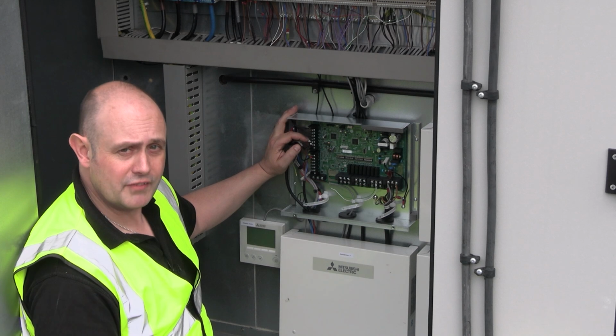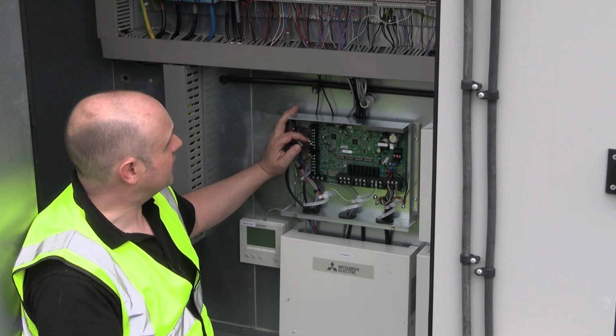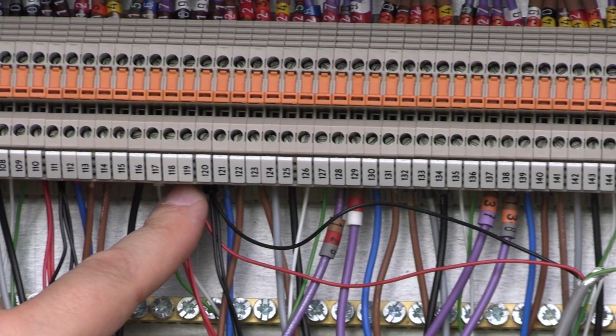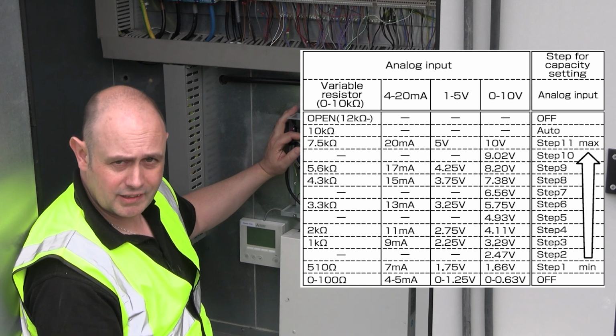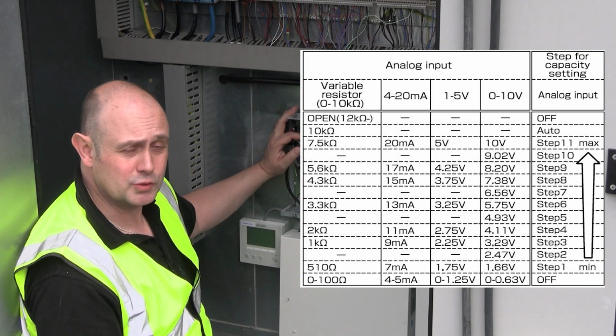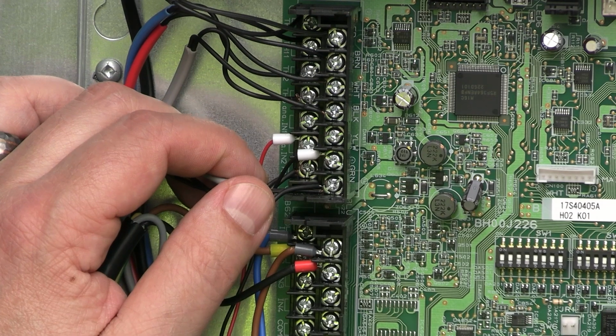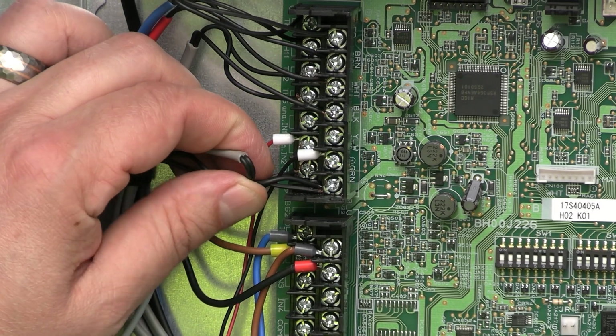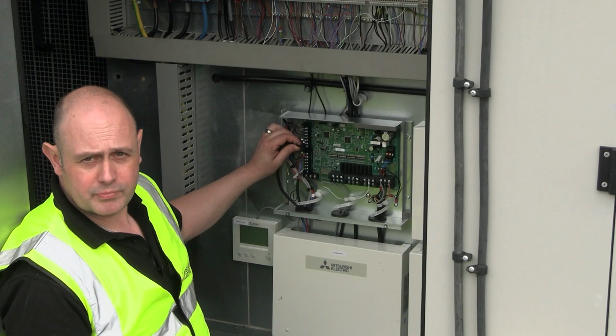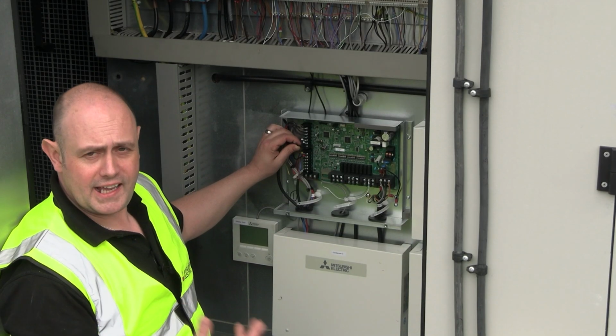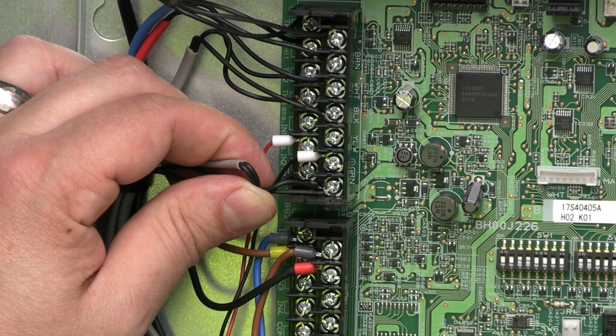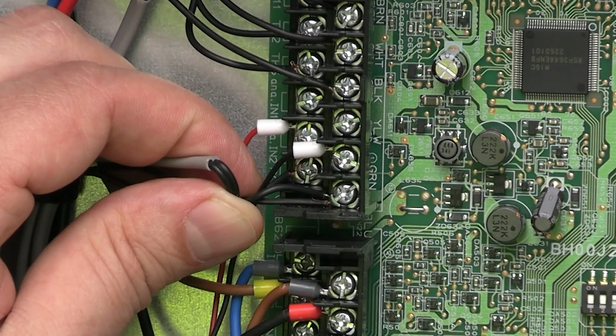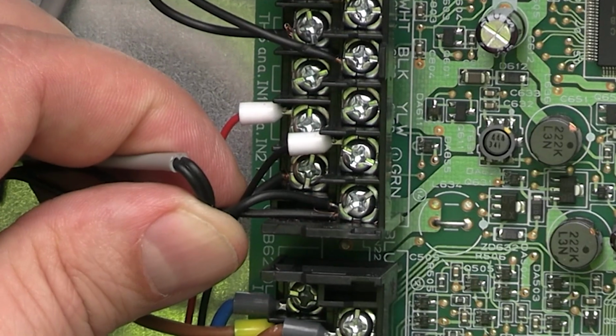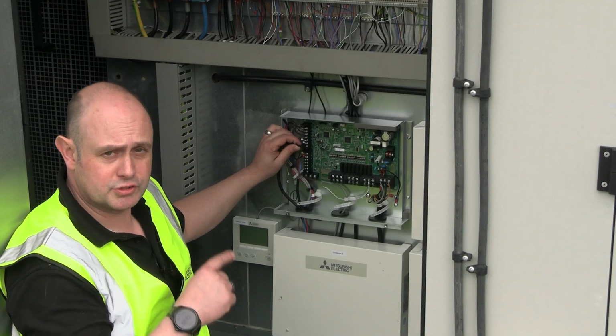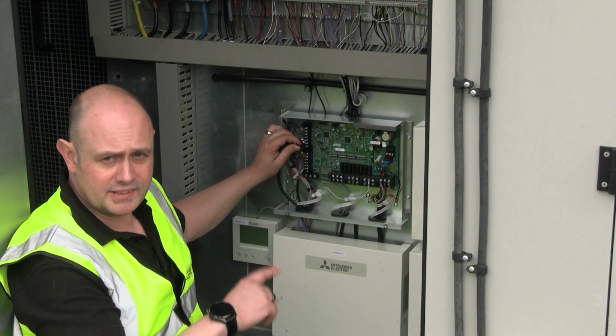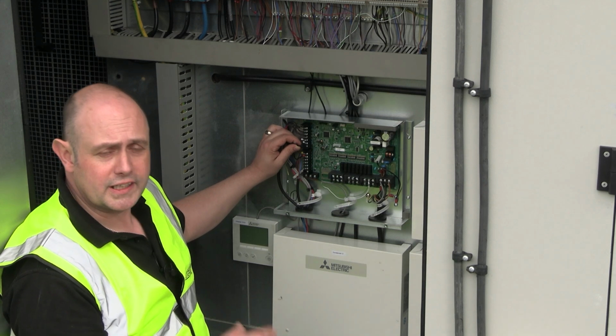So they're using a 0 to 10 volt signal from the air handling unit controller, and we're feeding that through onto the actual PAC-IF. So we've set the dip switches on there to tell it is working on a 0 to 10 volt signal. On the board we've got connections here marked as RC, so this is for the remote control. As we've got multiple air handling unit controllers here, we've got 2 sets of cables going there. We've got one set of cable going off to the actual remote control itself, and then the other one is daisy chaining across to the next PAC-IF, and then from that one onto the next, onto the next, onto the next, so they can all get controlled together.